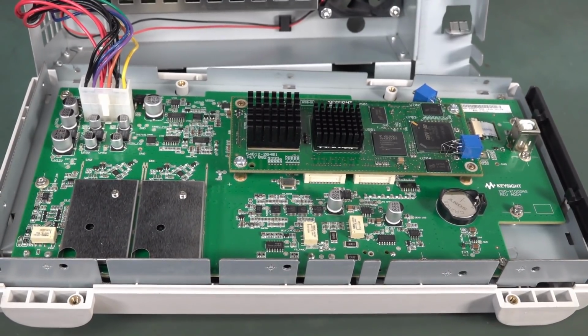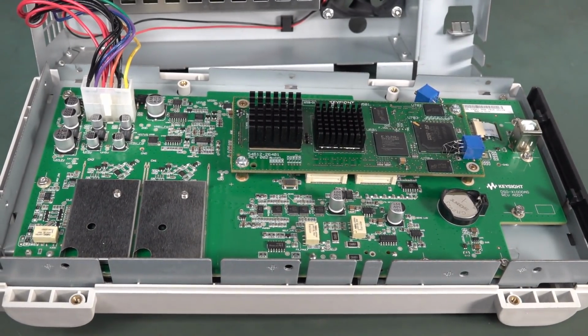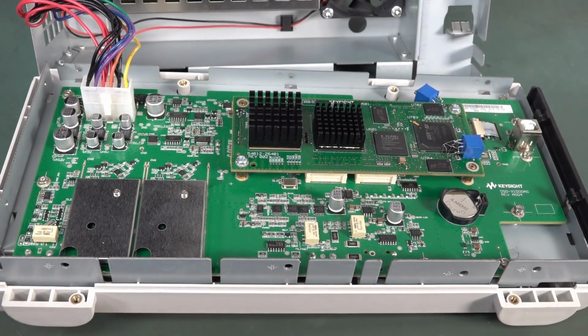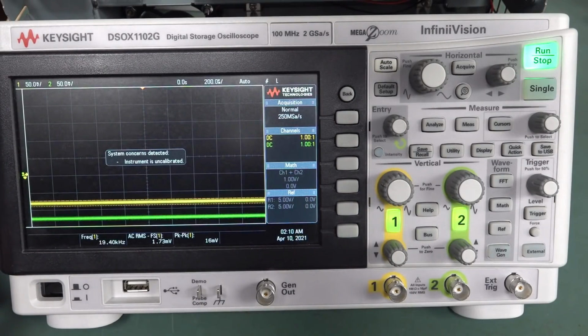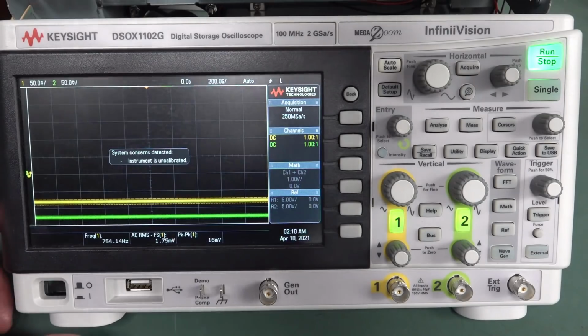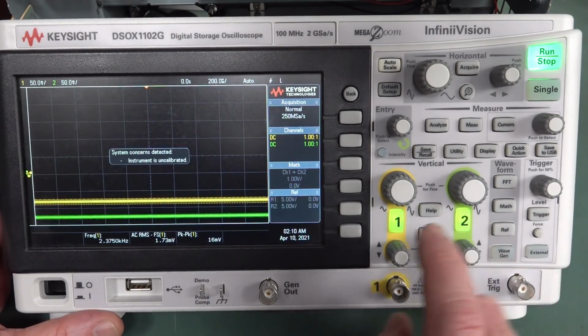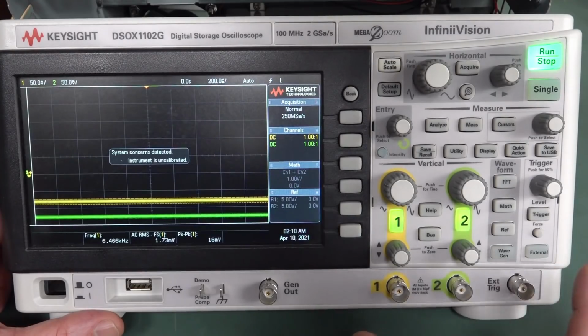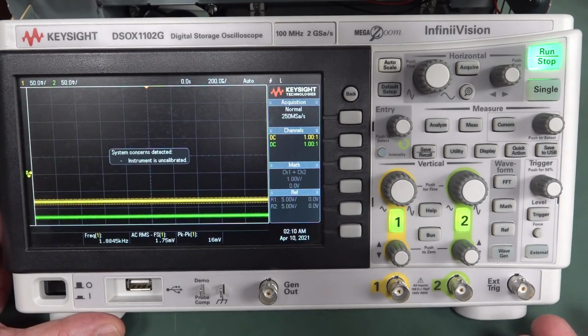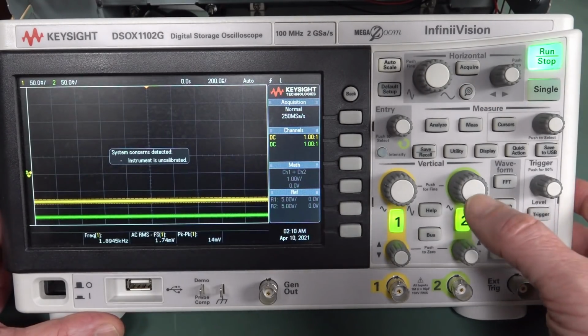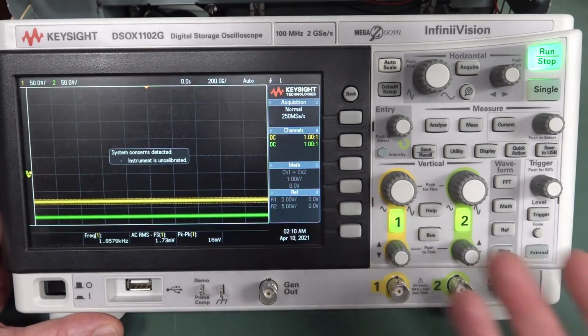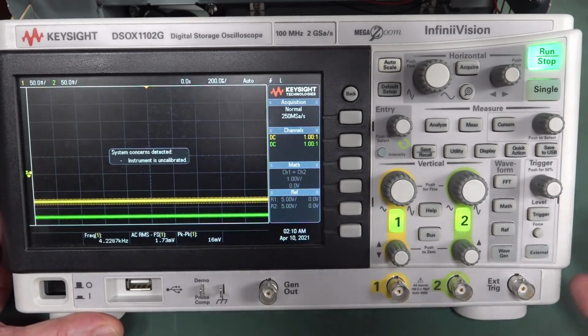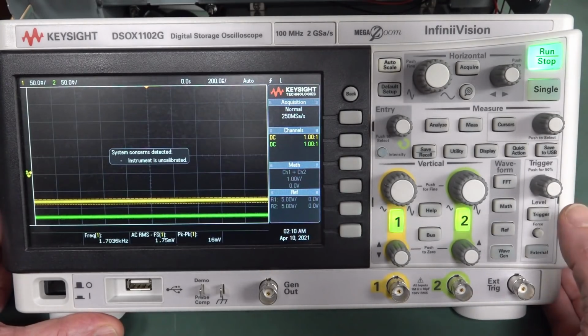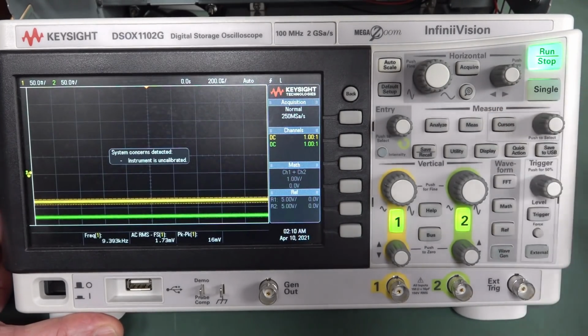Yeah, so this is not a Keysight failed instrument. This is a Dave fail. Yeah, I've done something horribly naughty to this. Okay, after that embarrassing revelation, don't hack your products, kiddies. You're going to come unstuck like Uncle Dave. Anyway, it seems to be a calibration issue. It says it's uncalibrated, and of course DC offset is part of the calibration. I think you can do an auto calibration for DC offset. So why it's lost this calibration, I don't know, because I remember at the time the hacked scope was working. So yeah, anyway, maybe I dicked around.